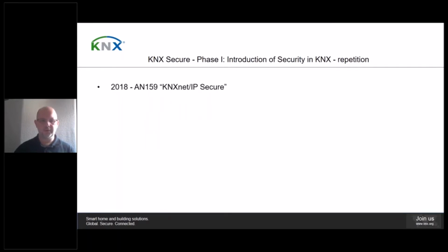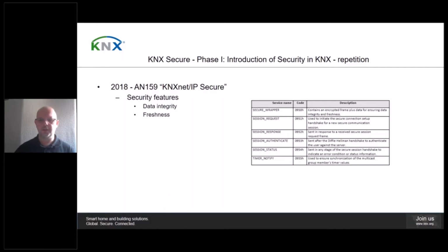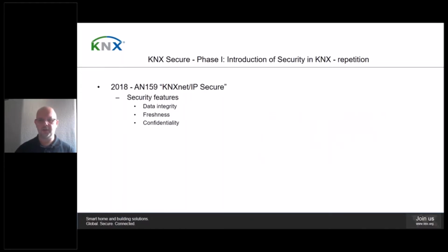The second part of the first set of KNX secure specifications is KNX NetIP Secure. This offers the following features: data integrity. This prevents that a hacker in a KNX installation that uses an IP network, a LAN, can inject manipulated KNX NetIP frames. Freshness. This is the protection against replay attacks. Confidentiality. This prevents that the hacker gains knowledge of what is going on in the building by observing the KNX message traffic. Authentication. This allows that the communication partners are able to trust each other.